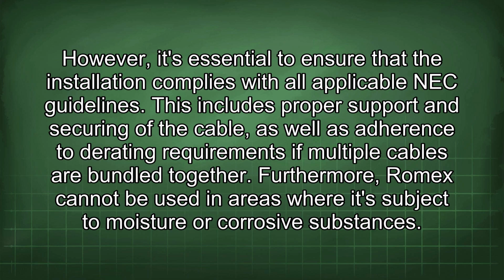However, it's essential to ensure that the installation complies with all applicable NEC guidelines. This includes proper support and securing of the cable, as well as adherence to derating requirements if multiple cables are bundled together. Furthermore, Romex cannot be used in areas where it's subject to moisture or corrosive substances.